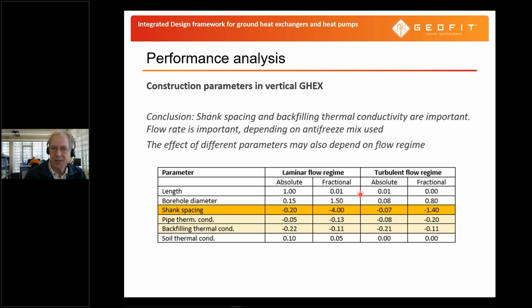Then the first thing we looked at are construction parameters for ground heat exchangers in vertical borehole heat exchangers. And we took a look at the length, the borehole diameter, the shank spacing, that is the spacing between the U pipe going down and the U pipe going up, the pipe thermal conductivity, the backfilling thermal conductivity, so the thermal conductivity of the pipe material and the backfilling conductivity of the borehole backfilling, and also the soil thermal conductivity. And we made this comparison for a laminar and turbulent flow regime.